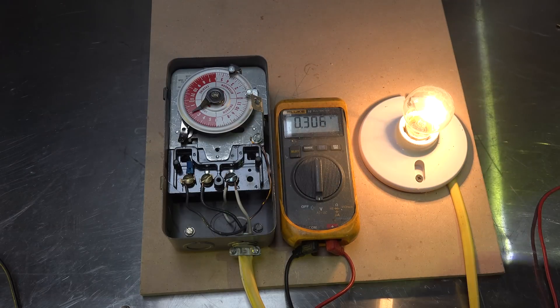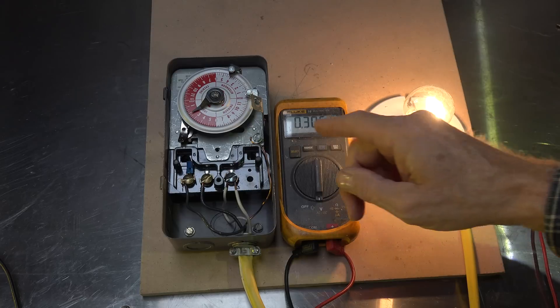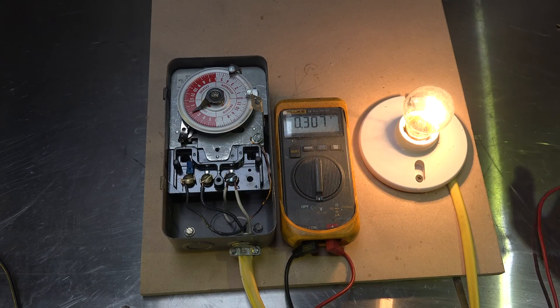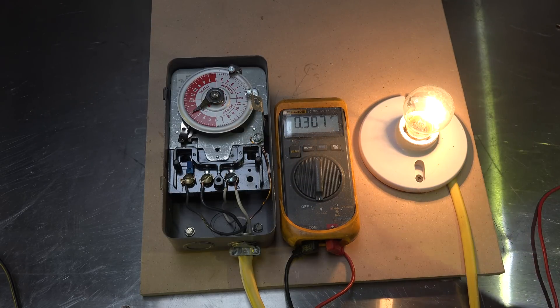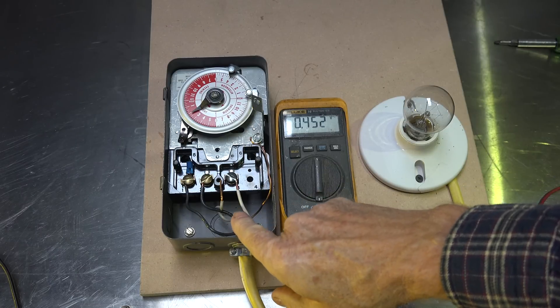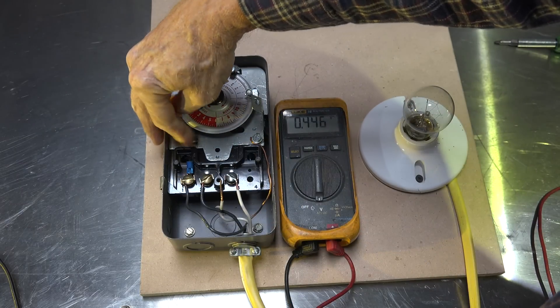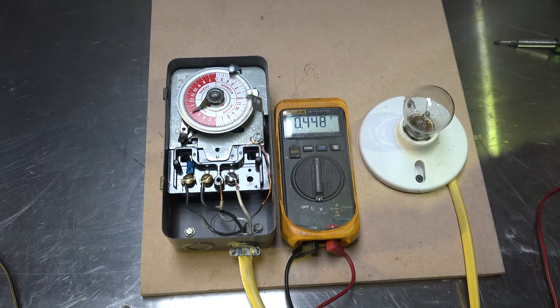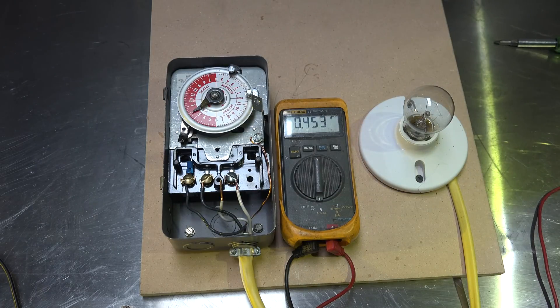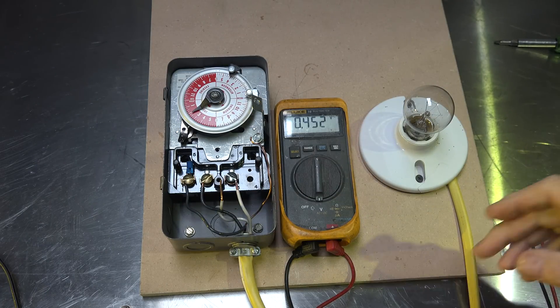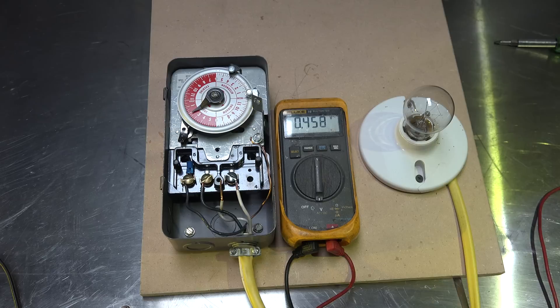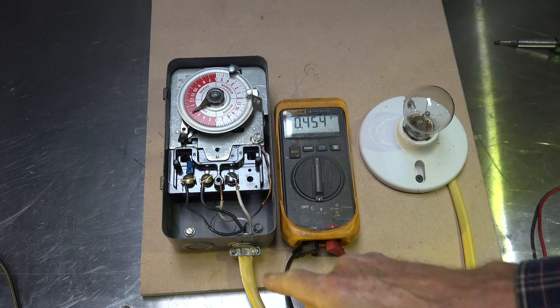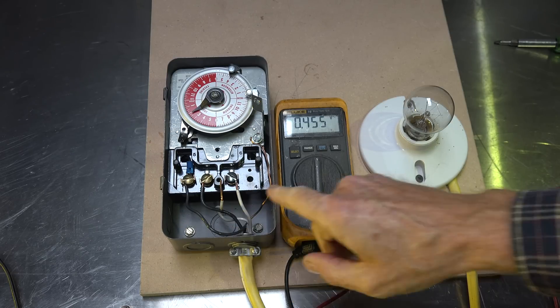Now if I disconnect, let's say the neutral gets disconnected. Now I've got the neutral disconnected right there. Nothing happens because there's no power going through the load and back. It comes up to the load through the hot wire, but when it comes back there's an open.